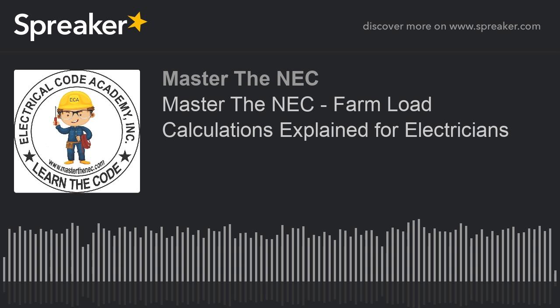Now, 62.5 amps is not more than the 65 amps that we first calculated as our loads that would be running simultaneously, right? So that tells us that the motor load is not going to be greater, so we get rid of that. So the largest load that we have right now is that 65 amps of simultaneous load that we determined by looking at all the equipment and how they're going to operate.